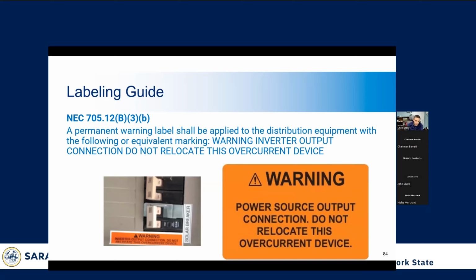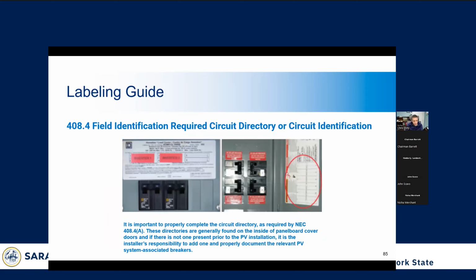Here's the power source output connection label. This shows where the PV power is coming into the panel. You want to make sure that it doesn't get moved. Obviously, it says do not relocate this overcurrent protection device, and you want to make sure that the label stays with the overcurrent protection device. This is again to avoid overloading the current to the bus bar.